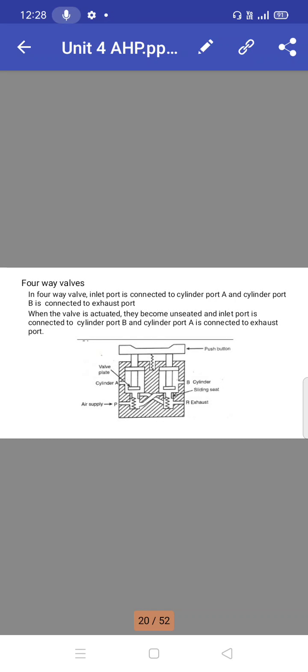Four-way valves: in a four-way valve, the inlet port is connected to cylinder port A and cylinder port B is connected to exhaust port. When the valve is actuated, they become unseated and the inlet port is connected to cylinder port B and cylinder port A is connected to exhaust port.